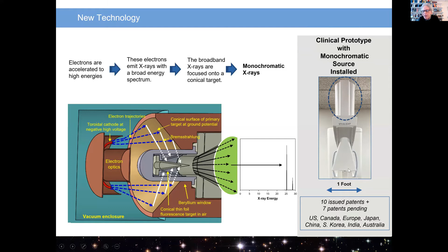So let's look at some of the spectral characteristics. Here is a monochromatic emission from the tube using a tin compact absorber. You see the K alpha and K beta lines from the tin. The monochromaticity of this source is 96%. Here are examples of a monochromatic emission from several other compact secondary fluorescers. And here's a list of potential fluorescers one can use for low energy and high energy work.